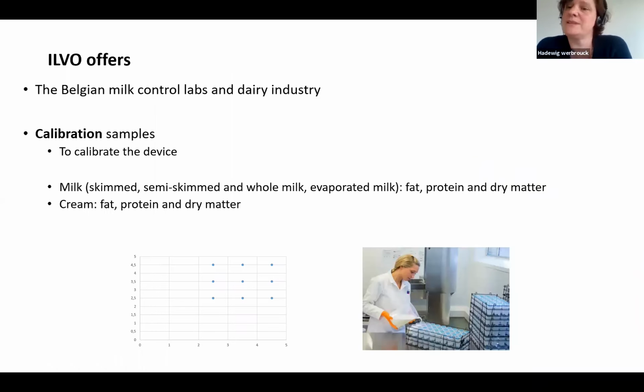ILVO offers, together with CRA-W Gembloux, calibration samples, proficiency tests, and control samples to the Belgian milk control labs and to the dairy industry. By using these samples, they are able to obtain accurate results. Concerning the calibration samples, with these samples, you can calibrate the device. As already said, this alternative method requires calibration to obtain accurate results. ILVO offers calibration samples for skimmed milk, semi-skimmed milk, full milk, evaporated milk, and cream for the parameters fat, protein, and dry matter.